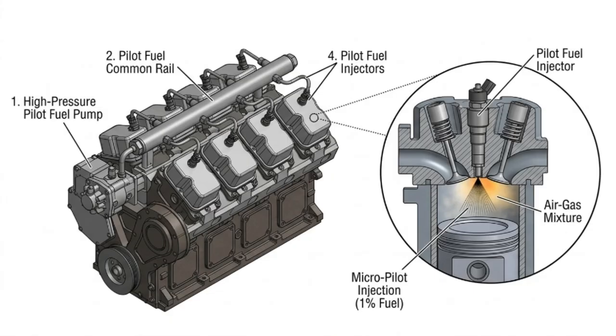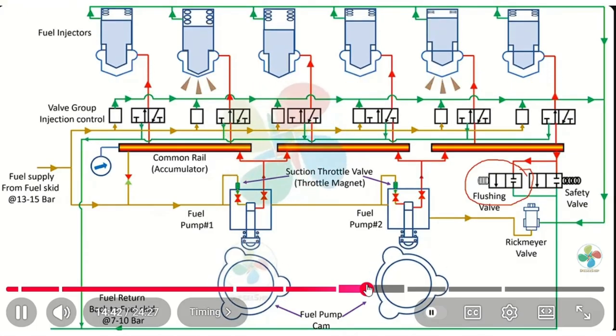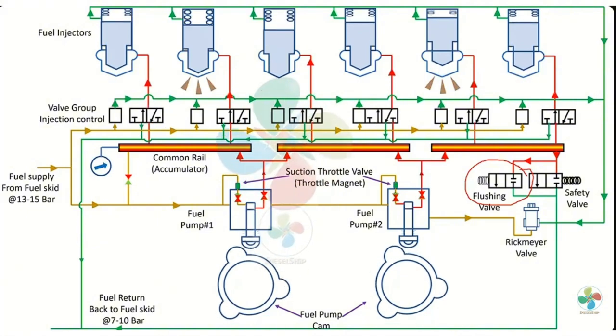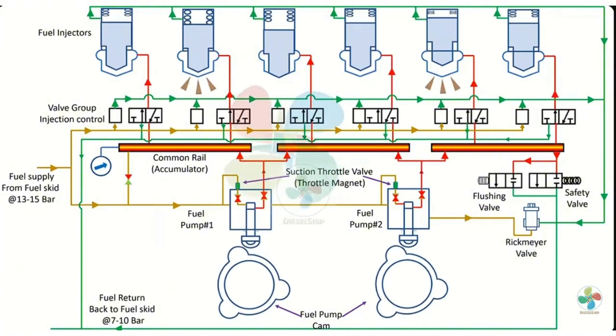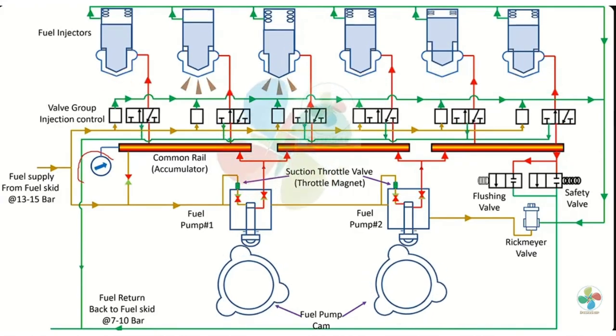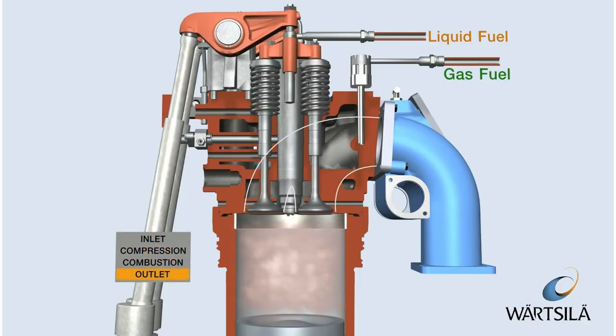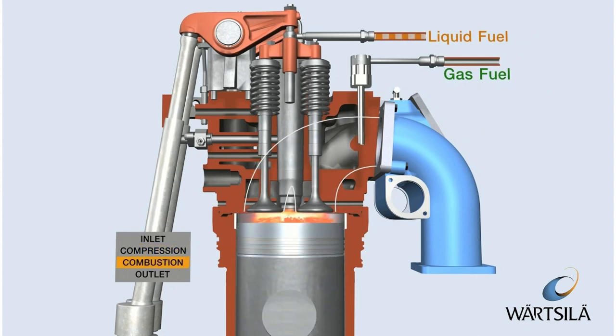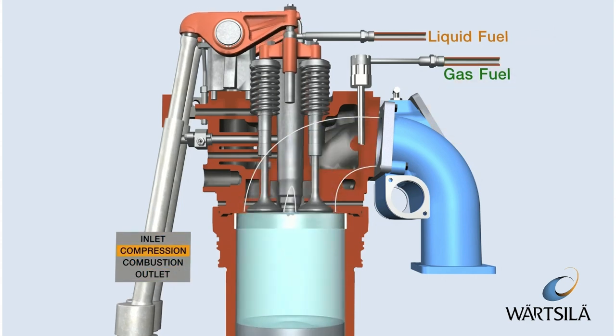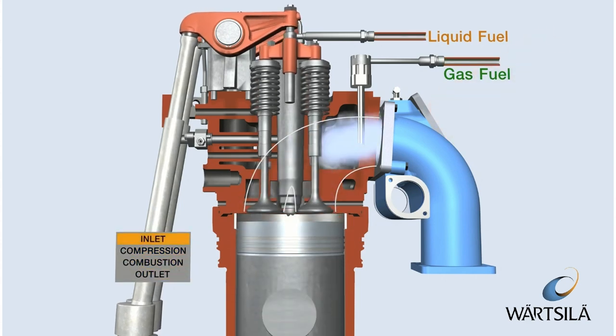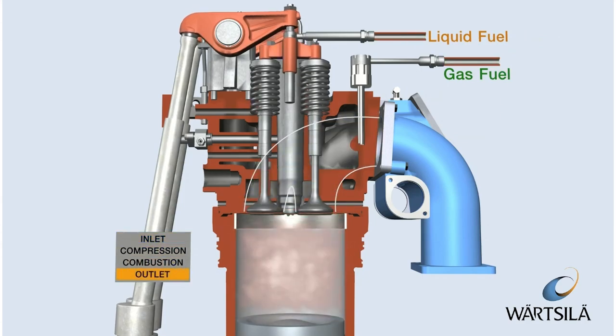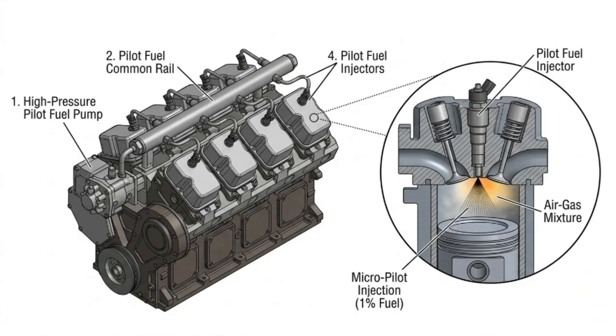In gas mode, the engine requires a small amount of pilot diesel to ignite the air-gas mixture inside the cylinder. This function is handled by the pilot fuel common rail system. A dedicated high-pressure pump supplies diesel into a common rail, where fuel is distributed to each cylinder injector. The pilot injectors then deliver a precise micro-injection of diesel to initiate stable combustion across the engine. Next, let us look at another critical utility system, the compressed air system, used for engine starting and operation.